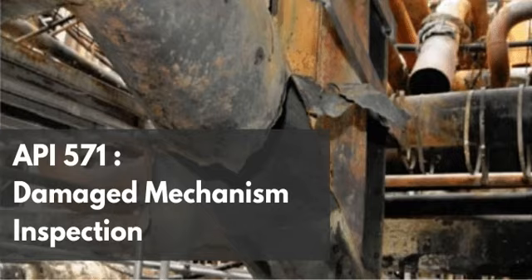And within the copper-zinc family, the text explicitly points out that the most notorious victims are heat exchanger tubes made of brass. Yes, and particularly specific grades of Admiralty brasses. Right. And I want to look at a highly specific case study that's documented here because it perfectly illustrates this. Well, let's hear it. So we have documentation of a catastrophic failure involving a very precise component. It was an inhibited Admiralty tube, UNS C44300 grade. A very common material, yeah. And it measured exactly 0.75 inches in diameter, Birmingham wire gauge 16. Which means it has a wall thickness of exactly 0.0463 inches. Very thin. Right. And crucially, it featured extruded fins.